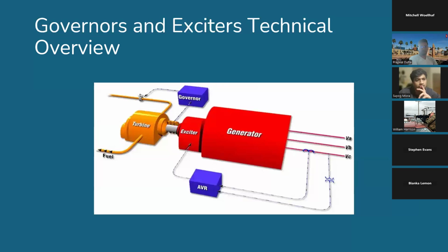However, they adjust the prime mover, in this case the diesel engine, which controls the generator's speed and maintains frequency stability. In PSCAD, and in the case of a diesel generator, governors are modeled as dynamic control systems that respond to frequency deviations by increasing or decreasing the fuel input to the engine. This helps keep the generator running at the desired speed, ensuring that it stays synchronized with the system.